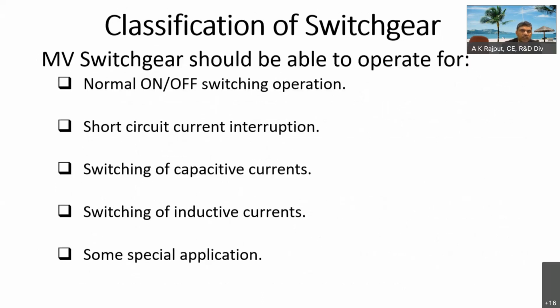What the switchgear in general does is perform the normal on-off switching operation. They are able to handle the short circuit current and interrupt it in a well-defined time interval, and the time sequence of operations is also defined. Sometimes the auto reclosure feature is also built into the protective devices, and after say 1 or 2 attempts of auto reclosing, the circuit breaker should go to the lockout condition. Otherwise, fire incidents may occur and more damage to the system can occur rather than saving it. Switching of capacitive currents is a slightly highly demanding duty, and similarly switching of inductive currents, and some special applications are also there.